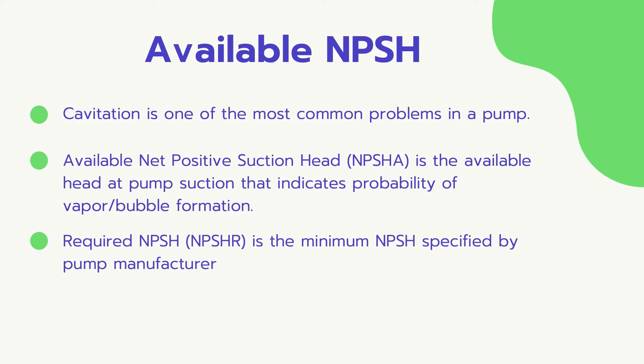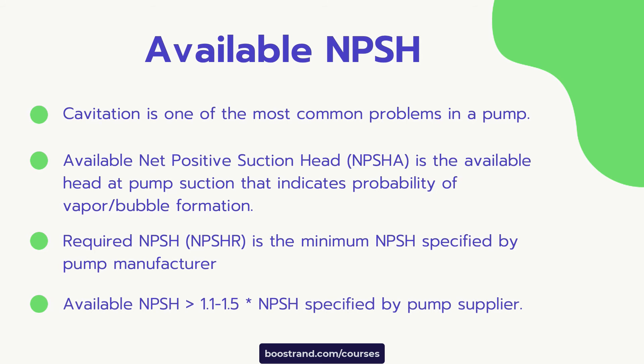So how much would this margin be? To avoid any process deviation from the NPSHA, we usually take the margin to be around 10% to 50%. This means that the available net positive suction head should be greater than 1.1 to 1.5 times the required net positive suction head specified by the supplier.